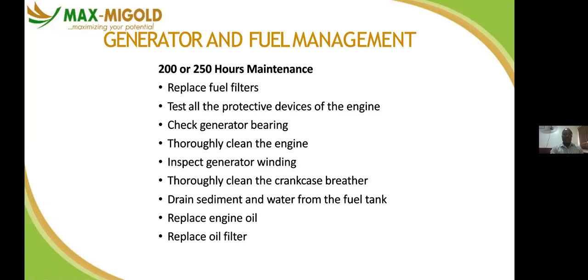Test all the protective devices of the engine. Check the generator bearing thoroughly. Thoroughly clean the engine. Inspect the generator windings. Replace the engine oil. Drain sediment and water from the fuel tank and replace all filters. This is what you do every 250 or 200 hours.